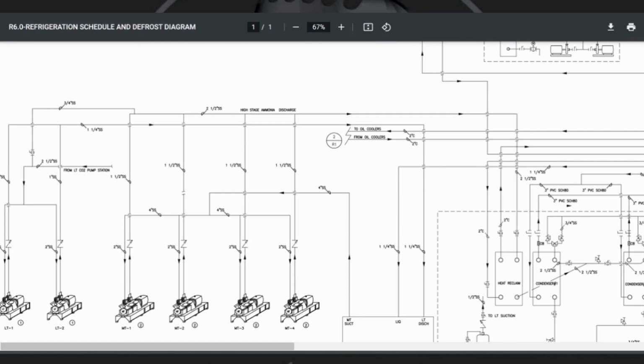Yes, plus we use very little natural gas because we're able to heat the store and the domestic hot water without using any natural gas. So overall, utility-wise, this is a very efficient store. But just on electricity, it's not as good as it could be, and when we build another one, we will correct those problems. We can't get away from the liquid pump problem, but we can certainly get down to, I'm going to guess, a 4 or 5 degree TD on the CO2 condensers.